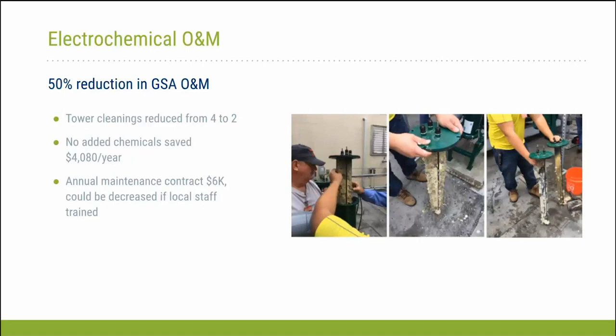The site normally had used about $4,000 per year in chemicals, and those were removed. We did add in a maintenance contract for the system that was $6,000 a year. That was just kind of a standard contract. That can vary depending on the location of the site and how far the travel time is. But also, if the site personnel are willing to do more of the cleaning of the system, that price can be reduced as well. And you can see the pictures on the right. We were at the site when we pulled the system. You basically pull this centerpiece out of the middle of the tube, and you can see all the scale buildup, all the material that was removed. And the cleaning of the system that we witnessed, honestly, was fairly straightforward. You could take a knife to this stuff, and it came right off of these systems.